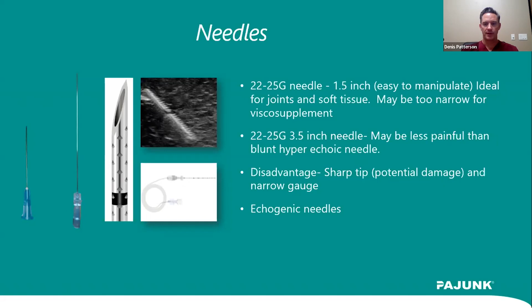And then the other thing I want to highlight is the surface of the needle. Do you go for a hypoechoic needle, which means that it's harder to see, or do you go with a hyperechoic needle? That's what we're trying to show here on the left, a hyperechoic needle that, under your ultrasound, will reflect the beam back to the probe and pick up a better signal. And that's what Pajunk is trying to do.